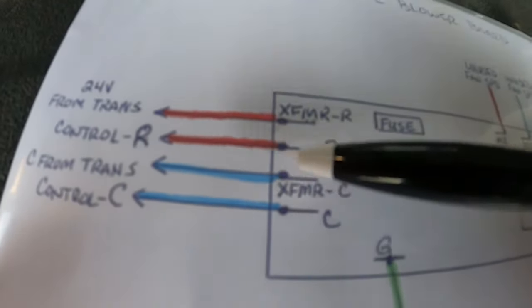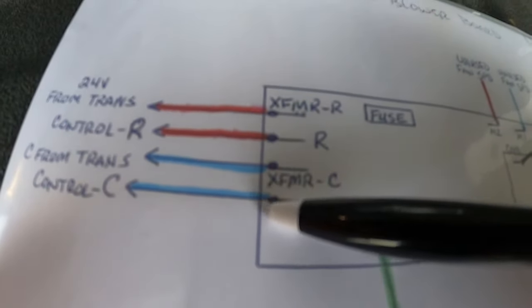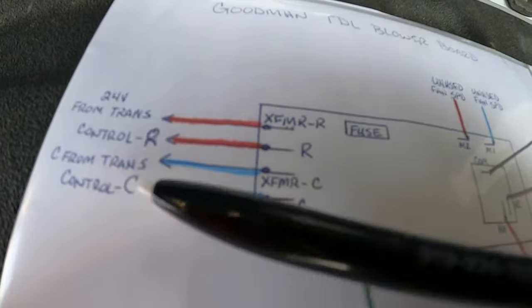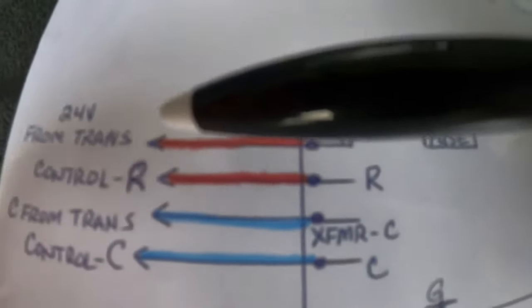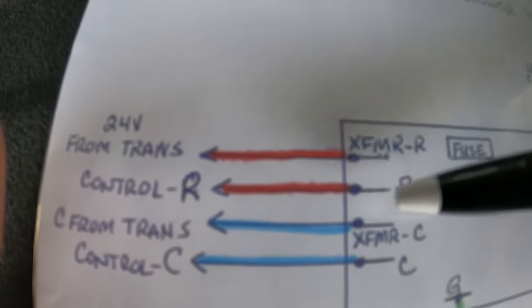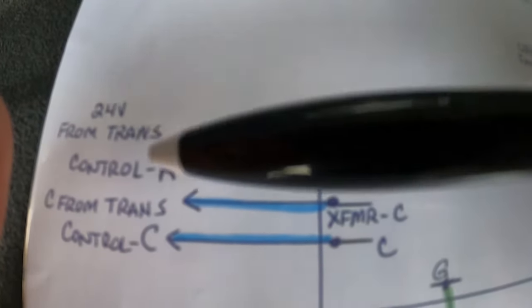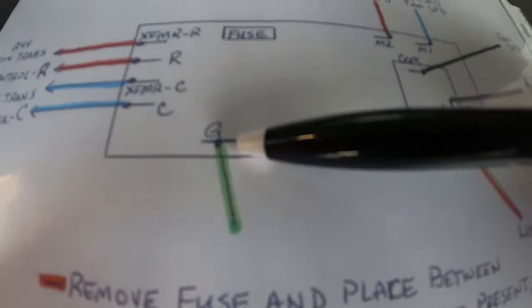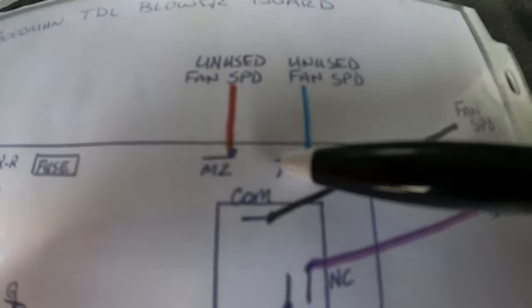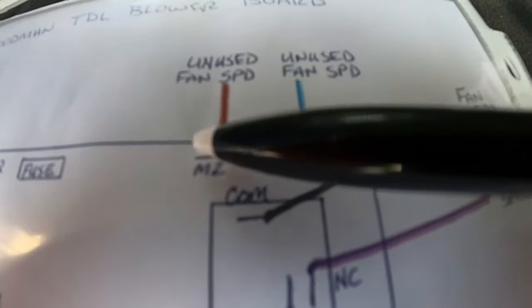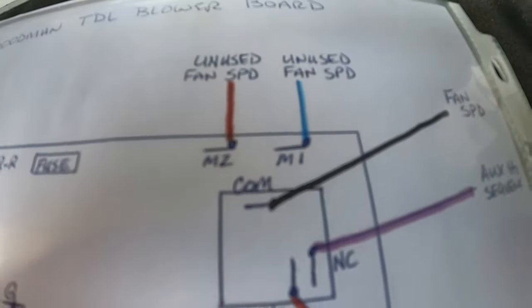You're going to have your commons. You're going to have common in from the transformer. You're going to have your common that goes back to your bundle of wires that you tie your thermostat to. You're going to have your 24 volts R from your transformer. Then you're going to have your R feeding back to your controls that you'll tie your thermostat to. You've got a fuse right there. Then you've got your G. It will have unused speed tap wires. Most of your motors will have a low, a medium, a high, maybe a low, medium, high, high. So you're going to have these M1 and M2 terminals. These are going to be basically your unused blower speeds.